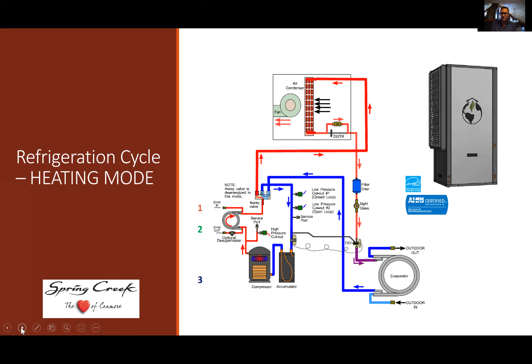You compress that gas and it creates heat, and that heat you then distribute through pipes to your fan coil or through in-slab heat. In my big buildings, geothermal heat pumps take the hot temperature, usually 110, 120, and put it into a distribution tank. From the tank, it's just distributed throughout the building. But you can also have GeoExchange units with built-in fans that blow the hot air into the house. And from there, we have this evaporator where we expand the gas, and we get that warm water from the field that's maybe 7 to 10 degrees. We usually take 3 or 4 degrees delta T out of that warm water, and the fluid goes back to the field at usually 3 or 4 degrees less. It gets reheated by the ground. That's why it's GeoExchange. It comes back at that 7 to 10 degrees again, and the cycle continues.